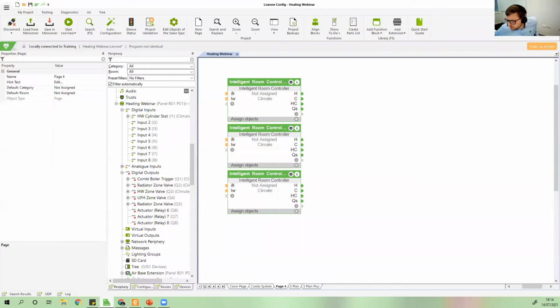Bill, on controlling hot water, it depends if it's an unvented or open vent cylinder. Unvented must have a non-resetting over temperature cutout wired in series with the heat source. There you go, there is your answer from a plumber. Sorry, Bill, no, not plumber, heating engineer. Really sorry about that. So there's your answer from a professional heating engineer. So it depends if it's unvented or open vent.